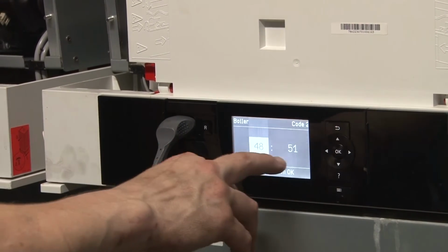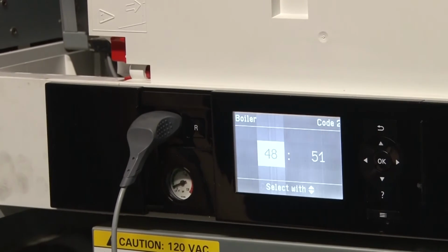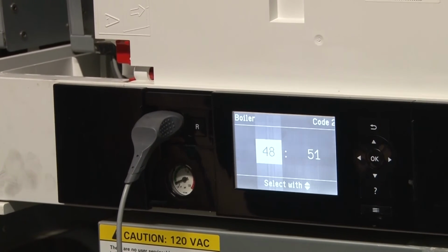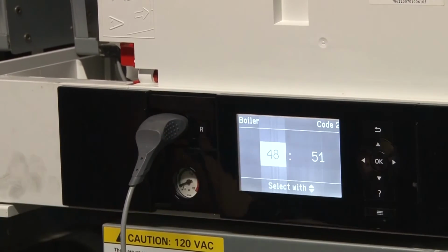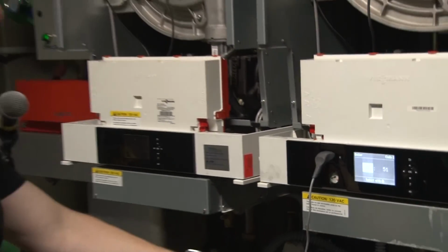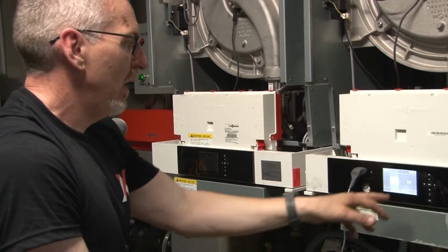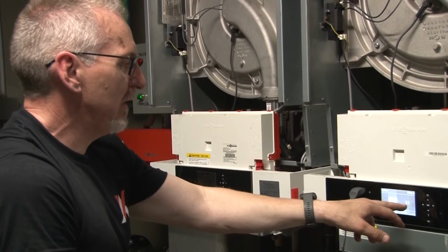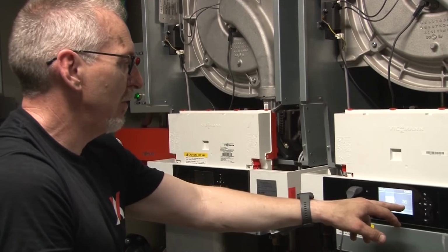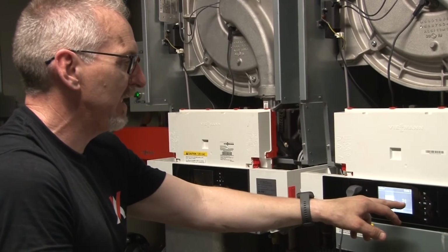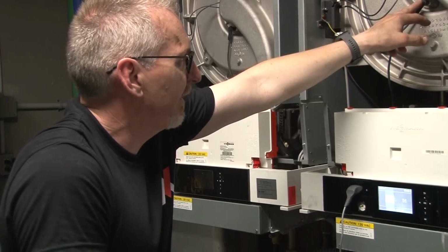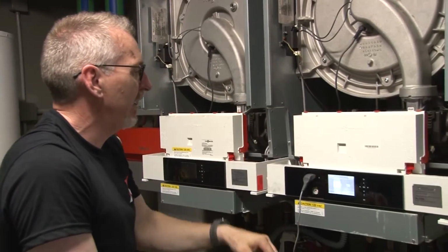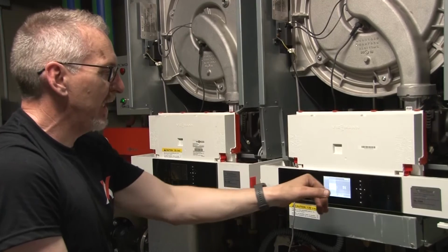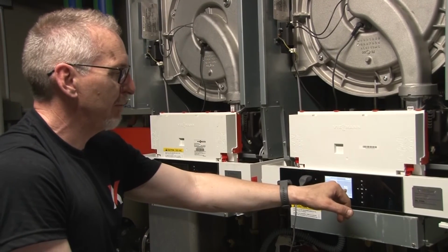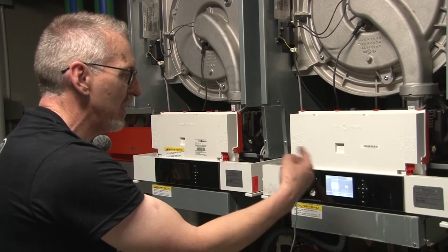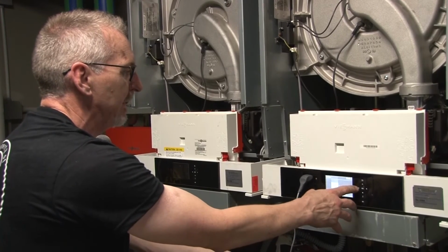This number, 48, tells me the quality of the ionization on ignition. Anything above 10 is what we're looking for. So at 51, we're at a really nice number here for this boiler. And as this drops, this is an area that you can check. If you're doing some maintenance and you come to address 48 and you see it down below 10, you can take the ionization electrode out, give it a little scour, pop it back in again. Then when the boiler fires again, if you go back to address 48, you'll have a reference, and it'll probably be a little higher than 10 at that point in time. It tells you if your ionization electrodes are starting to wear out.